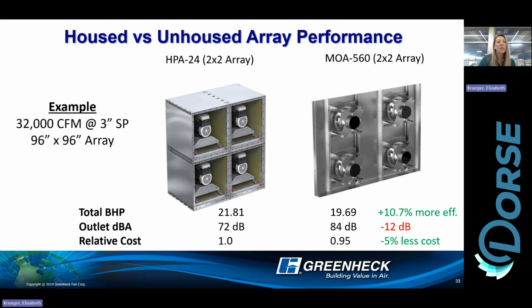So just a quick look at maybe why we would want to go to the MOA here. The brake horsepower is really what stands out to me here. The MOA tends to be about 10% more efficient when we're talking about a 4 fan array, right? Once we get more and more, think about adding an 8-fan array in that, we're going to end up saving more in the overall cost for operation over time. So that's where, for me, the big savings is going to be. Initial cost is slightly less, and over time, your MOA options really tend to stand out.